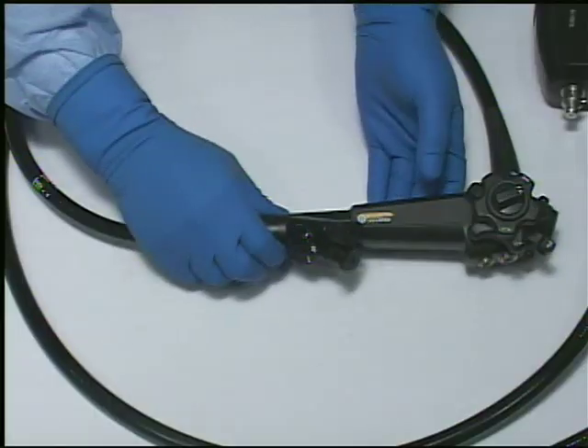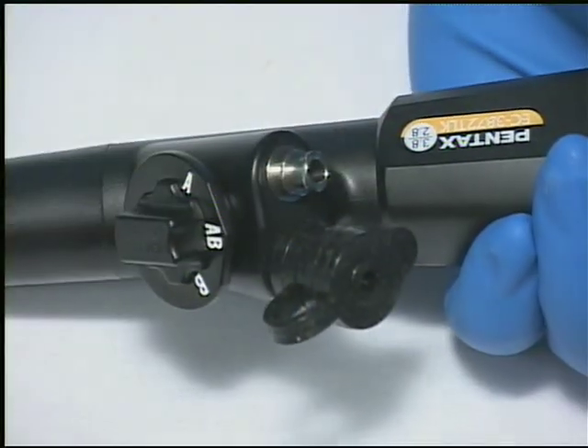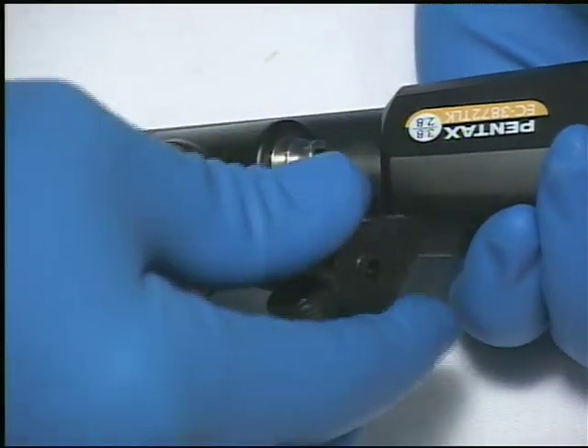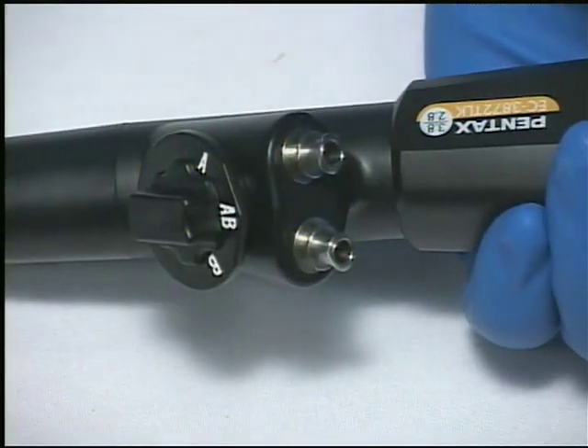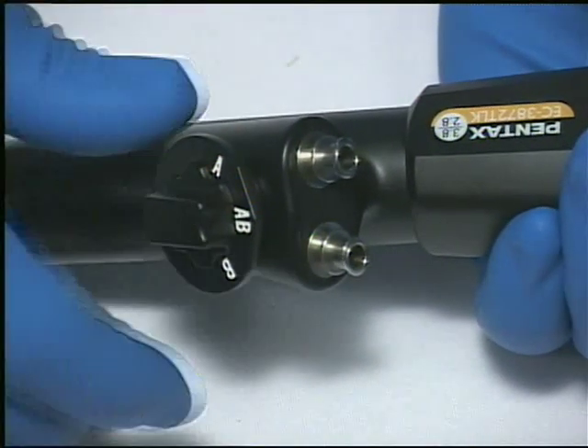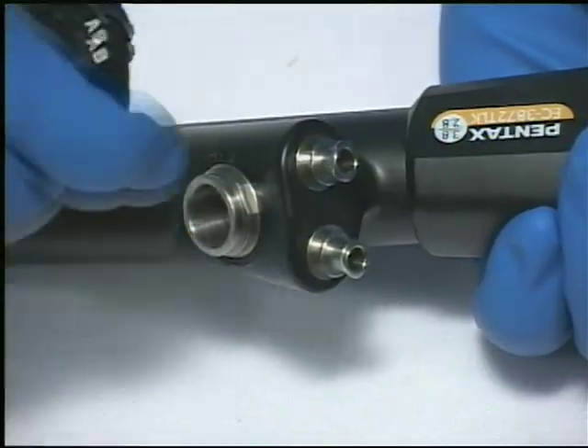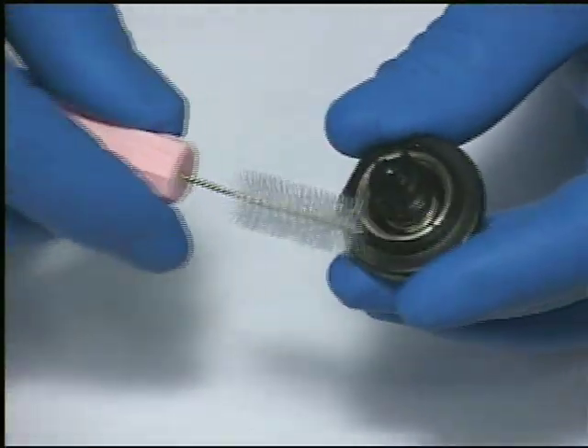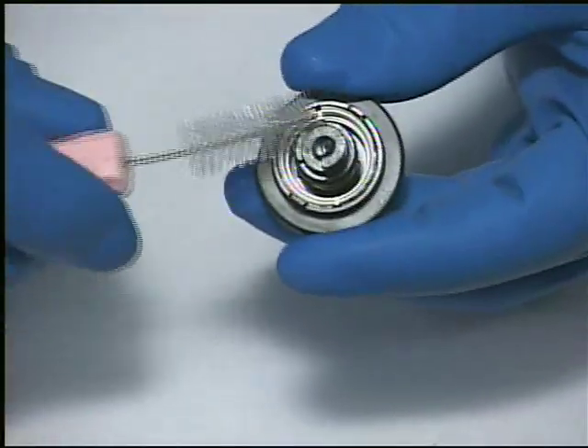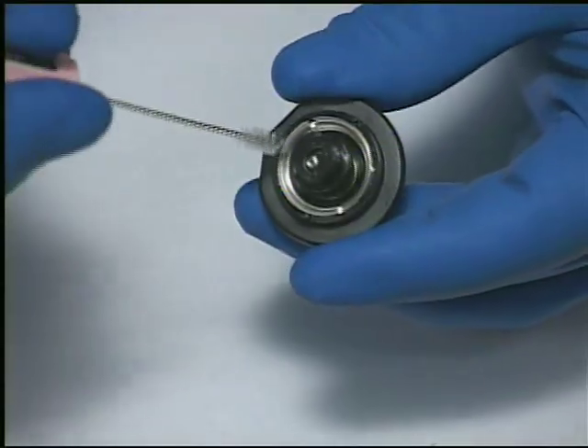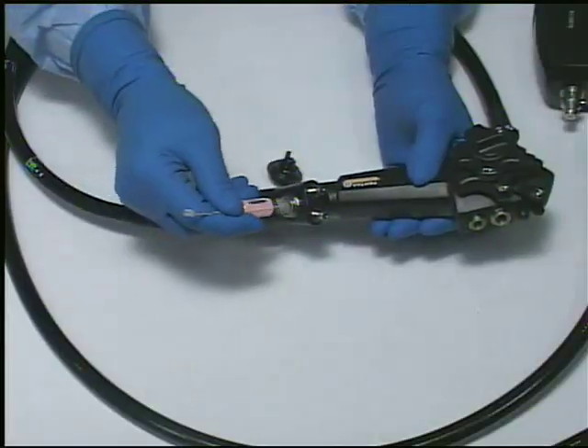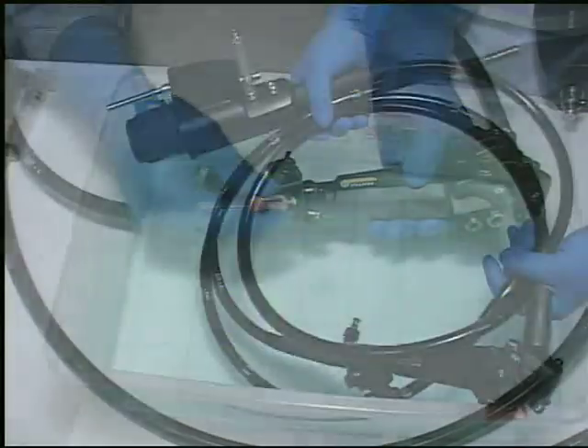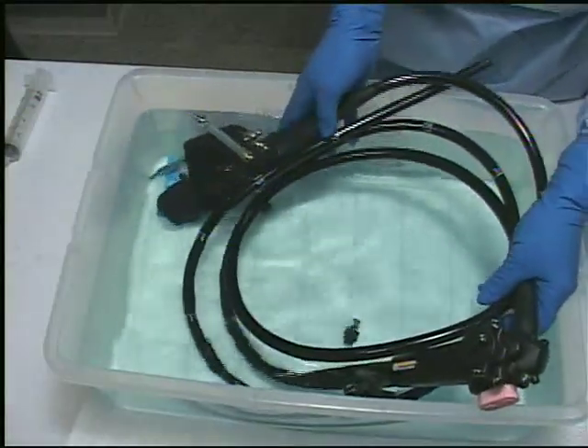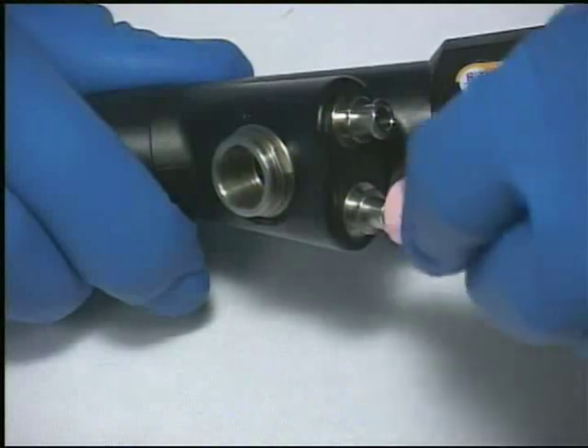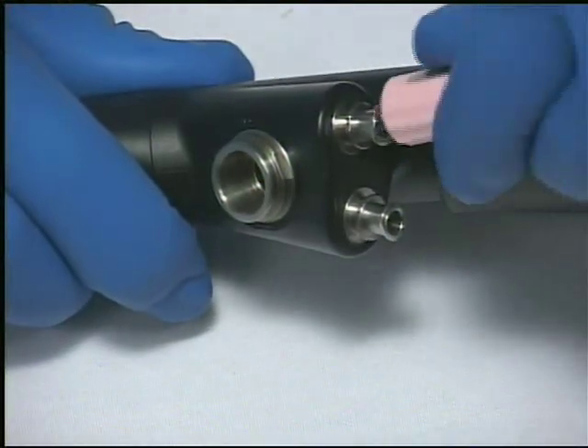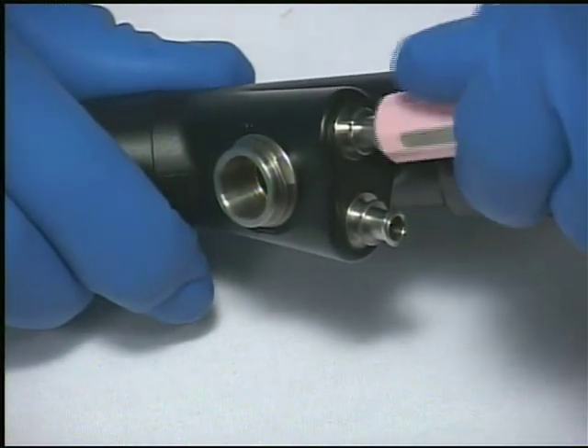During reprocessing of the Pentax two-channel 70, 72, and 70K, 72K series colonoscopes, the suction channel selector mechanism OFB161 must be removed from the colonoscope and thoroughly cleaned. This includes brushing of the selector mechanism as well as brushing of the receptacle for the suction selector, followed by exposure to an appropriate cleaning solution. Both the small and large instrument suction channels must be thoroughly brushed clean.